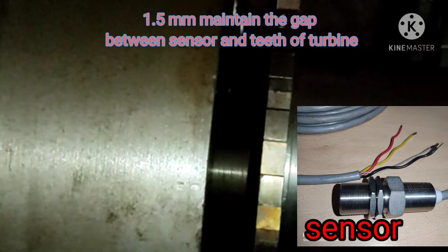We have to maintain a 1.5 mm gap between the sensor and the teeth of the turbine. This is a required measurement, and due to this we are going to tighten our sensor probe.